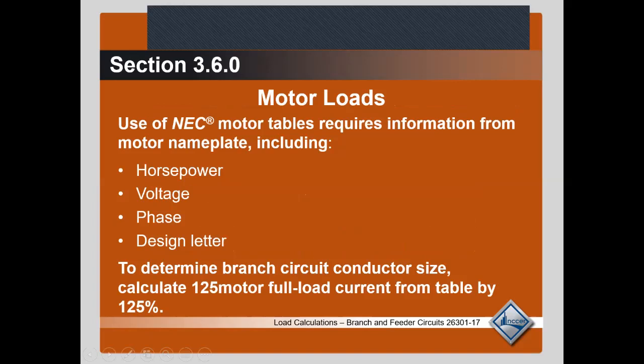Use of NEC motor tables requires information from motor nameplates, to include horsepower, voltage, phase, and design letter. To determine branch circuit conductor size, you'll calculate the motor full load current from the table by 125%.